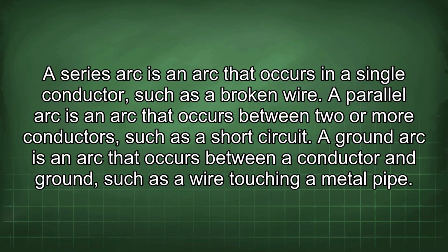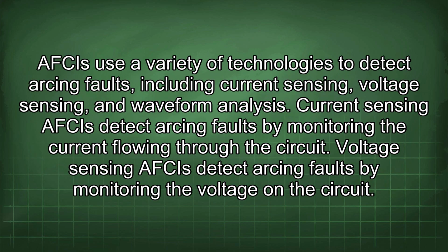A series arc is an arc that occurs in a single conductor, such as a broken wire. A parallel arc is an arc that occurs between two or more conductors, such as a short circuit. A ground arc is an arc that occurs between a conductor and ground, such as a wire touching a metal pipe. AFCIs use a variety of technologies to detect arcing faults, including current sensing, voltage sensing, and waveform analysis.